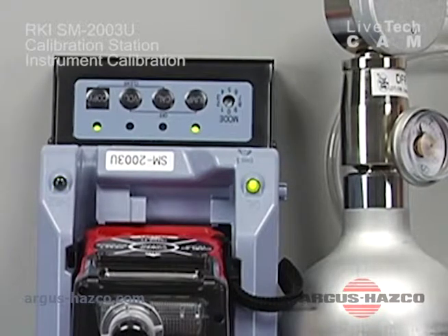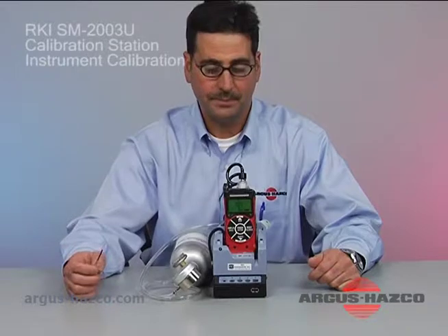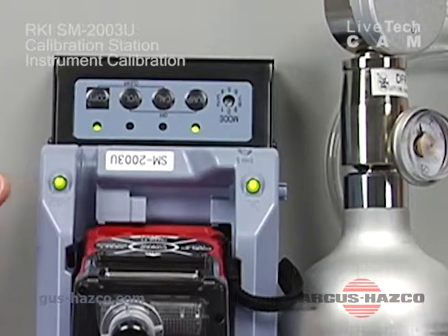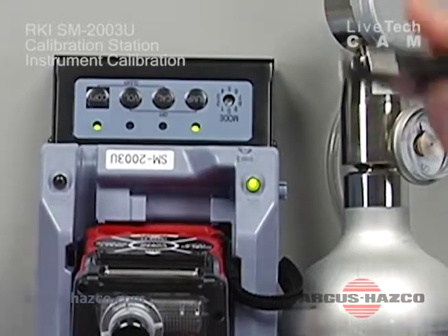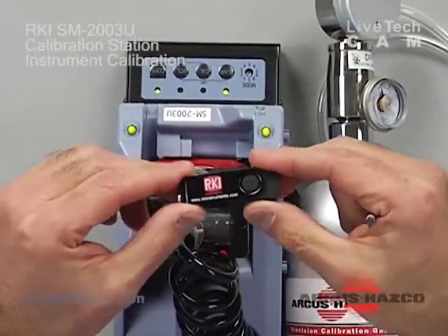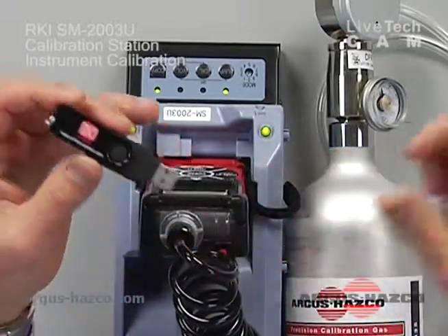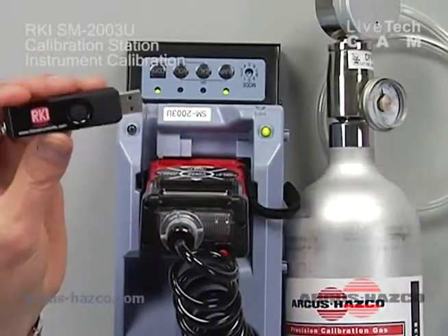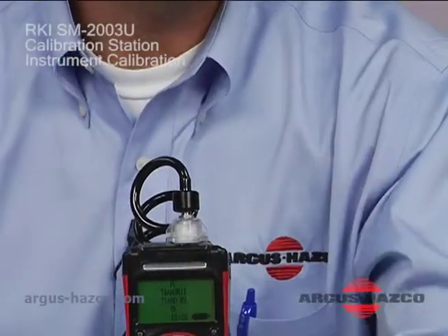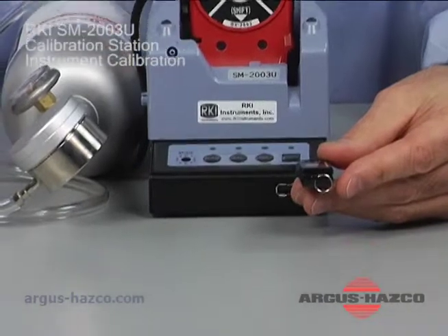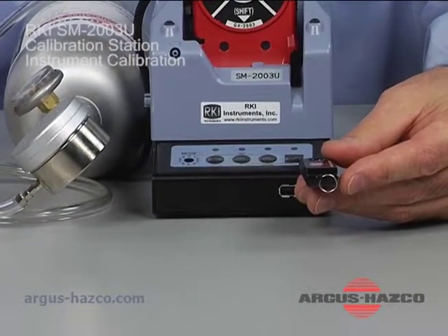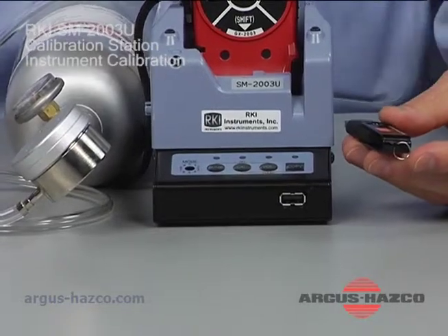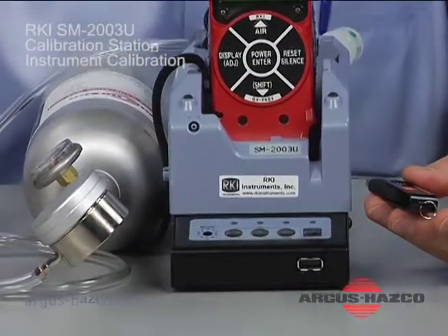Automatically, everything is stored within the standalone cal station itself, which can then, at your convenience, be retrieved. You see this amber light flashing, that means it's charging. So with the unit in the dock, it is charging as well. To retrieve the information that is within the dock itself, you would use a thumb drive, a flash drive that's included, but it is up to you whether you use this or another. It does not matter. This is just what's supplied with the manufacturer. It's installed into the front of the instrument, and the copy button is pressed to retrieve all the information that is inside the cal station itself.